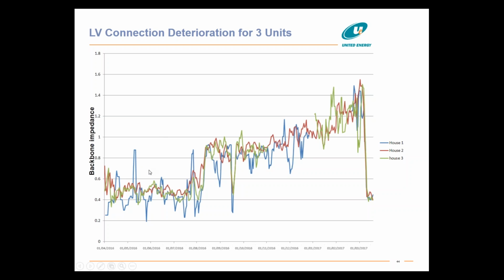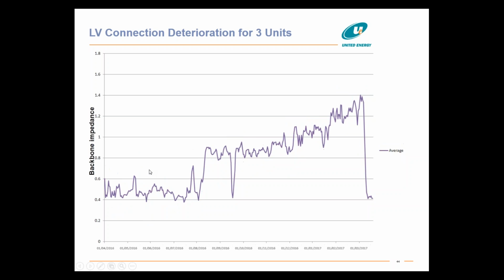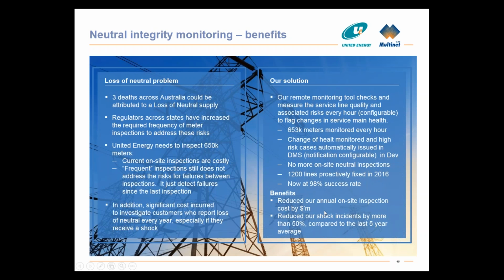This was a case of 3 houses, all supplied from a single pole. If we take the average, we see a similar pattern: all was good, then something happened, probably resulting in a bad connection. It got corroded and got worse until we issued the job, and then it restored back to normal.